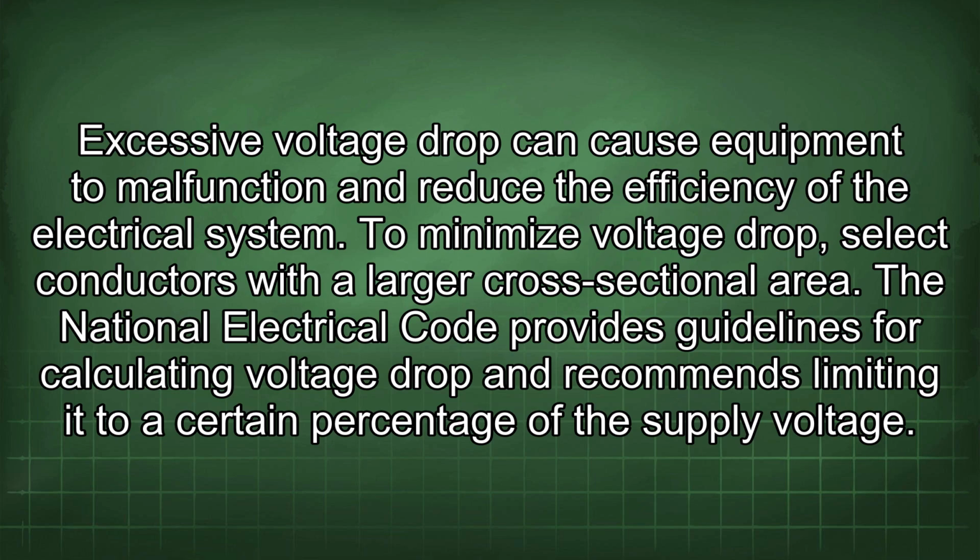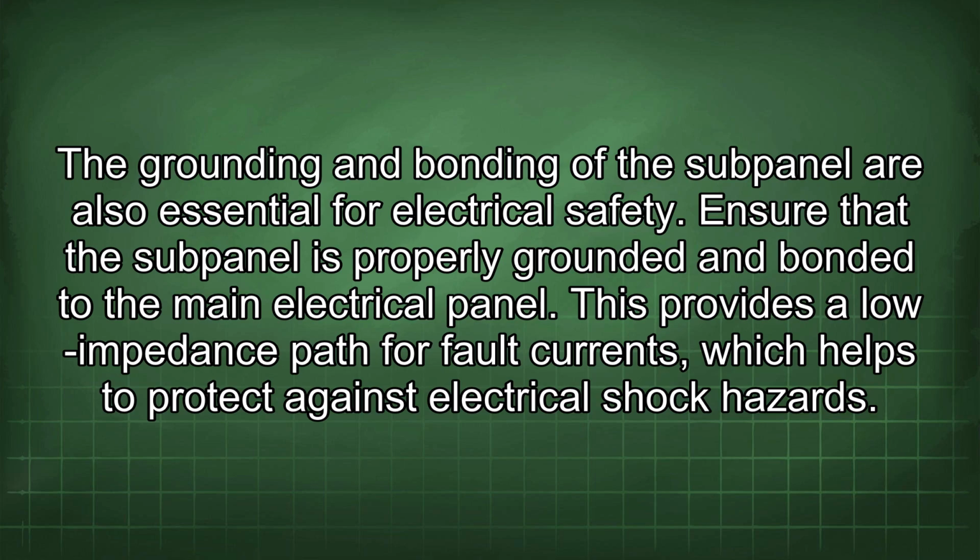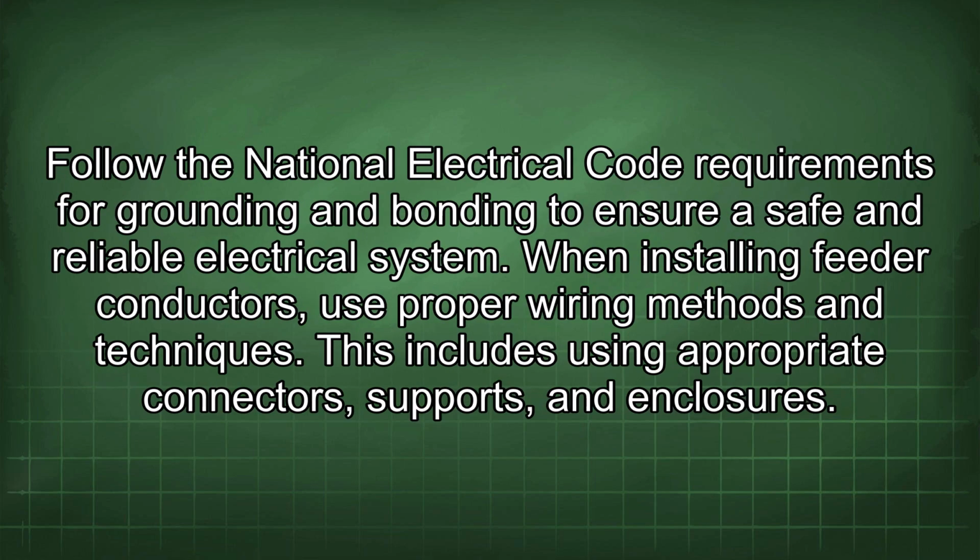supply voltage. The grounding and bonding of the subpanel are also essential for electrical safety. Ensure that the subpanel is properly grounded and bonded to the main electrical panel. This provides a low impedance path for fault currents, which helps to protect against electrical shock hazards. Follow the National Electrical Code requirements for grounding and bonding to ensure a safe and reliable electrical system.